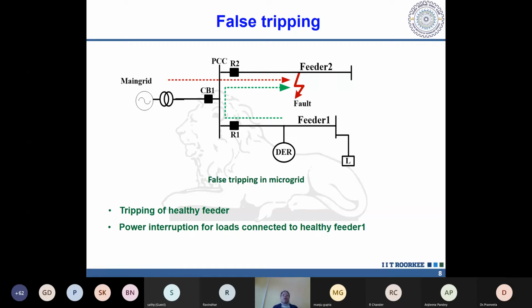It will also try to give a trip signal, because it will sense there is a fault. When the fault current magnitude increases beyond the set value, the overcurrent relay reacts, generates a trip signal, and the circuit breaker will open. So feeder 1, which is a healthy feeder, will be sacrificed. It will be falsely tripped. This process is known as false tripping. This is one of the most challenging issues, and we have addressed some innovative techniques to handle such issues.